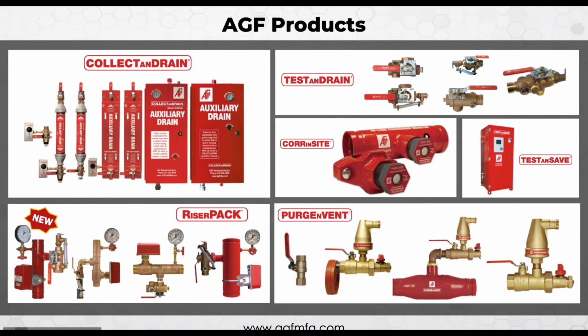On an annual basis, we recommend, because each of the CORR-in-Site plugs is dated, there's a date stamped into the units. If you were to utilize, say, our mechanical T version, the coupon that you would cut out of the pipe, we have a little notch in the product to attach the coupon to the CORR-in-Site, and that would become kind of your test device. So you would know, here's the pipe when it was brand new and installed at this location. Now my CORR-in-Site is indicating that I've lost a third of the wall thickness. I literally deduct one from the other, and that tells me what I have in remaining pipe. So from an annual inspection, the minimum we recommend is that you visually look at the CORR-in-Site to see if it's turned orange or not.